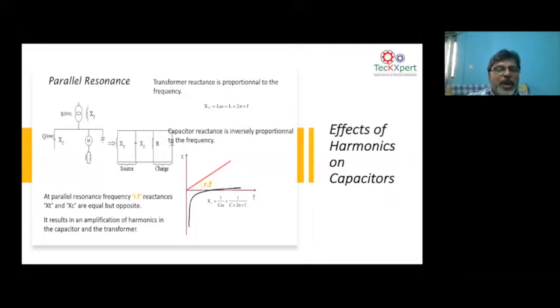And now when you have a harmonic producing load and you have a capacitor bank, which is a plain capacitor bank, it can create a parallel resonance. And parallel resonance, in the simple way of understanding, is that at the point of parallel resonance, your inductive impedance and capacitive impedance become equal and opposite. That is how parallel resonance is created. That means at the point of resonant frequency, your capacitive impedance and inductive impedance become equal and opposite. And in the process, a resonance takes place.